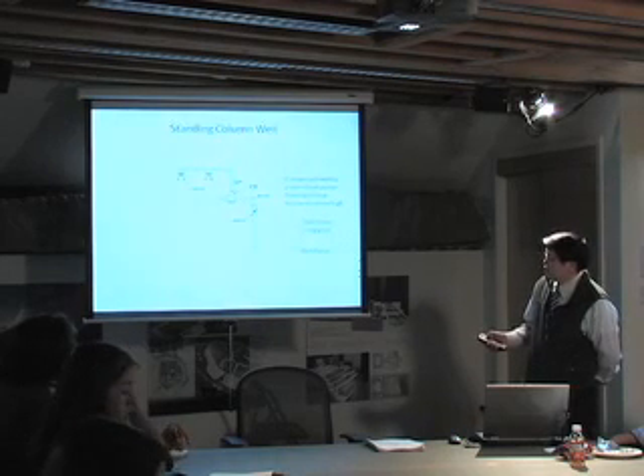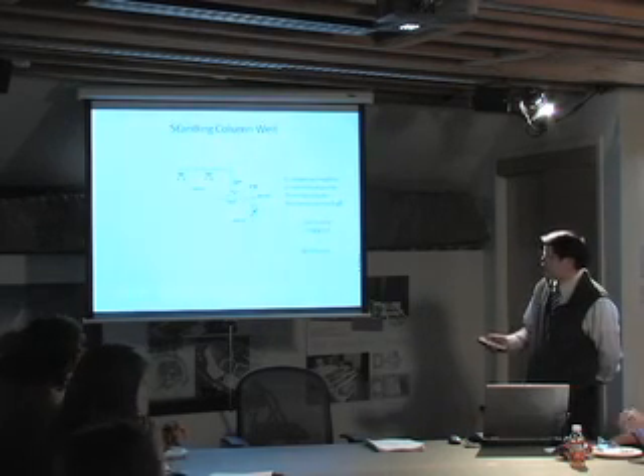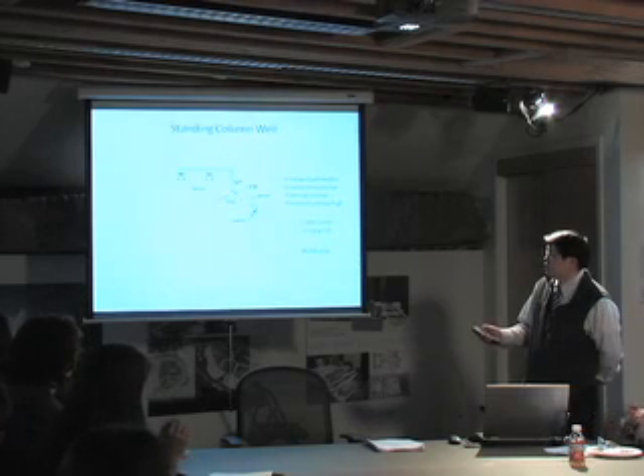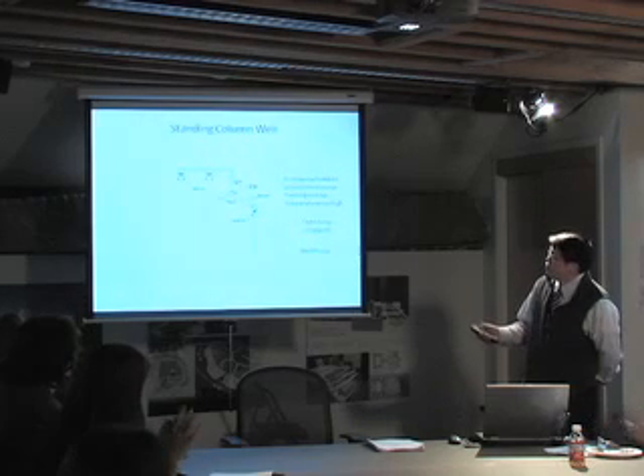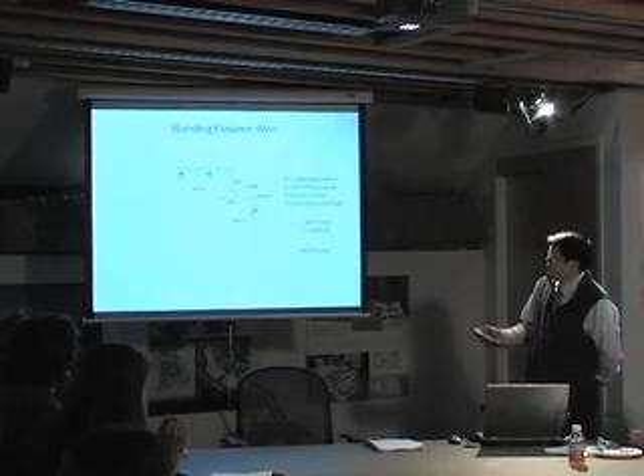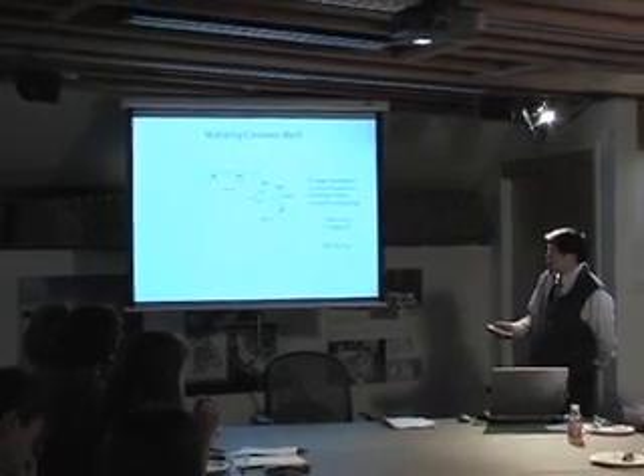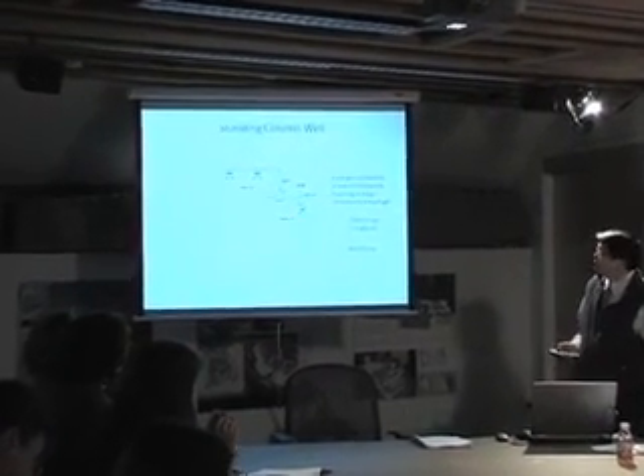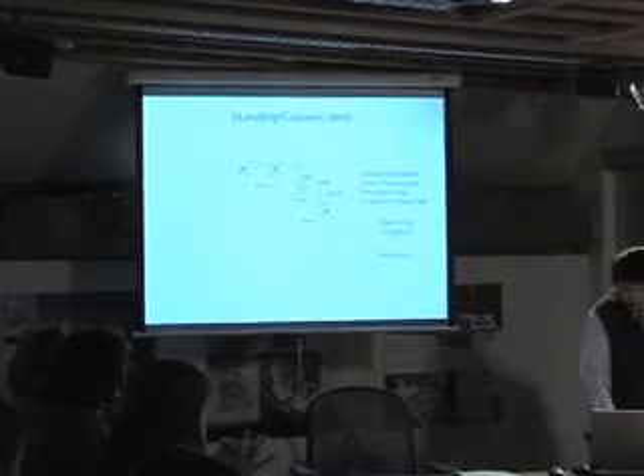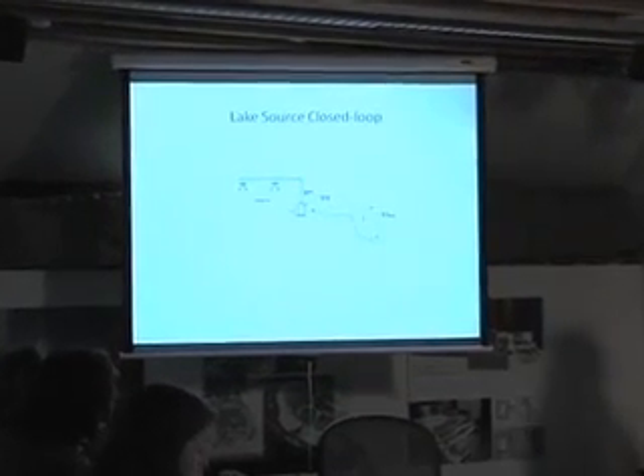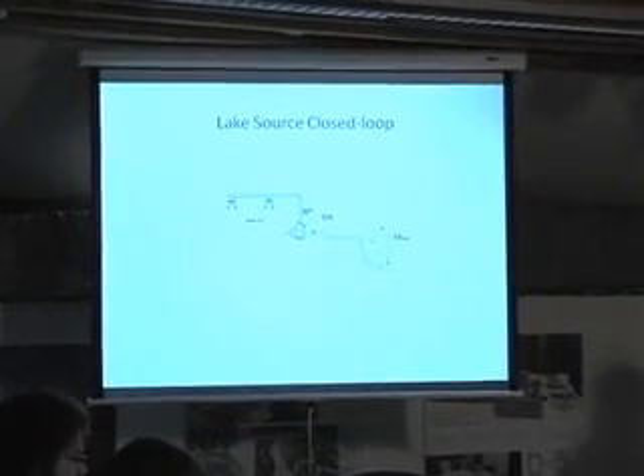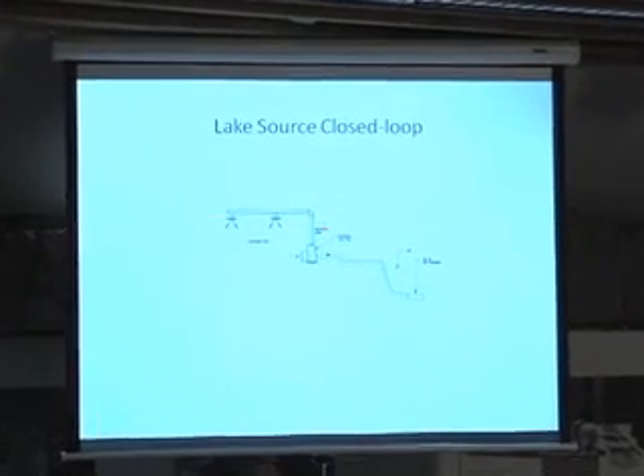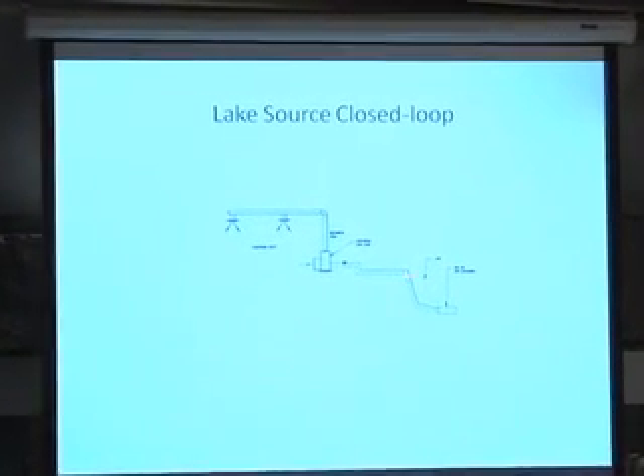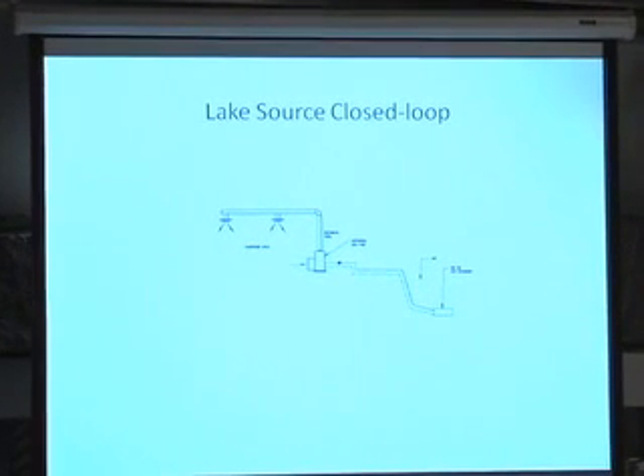And same deal for the cooling season. If the water gets too hot, as you are constantly rejecting heat into the well, you bleed some of the hot water here, and the surrounding cool water is going to make up to the well. Another configuration, if you have a large body of water near your building, like a lake or pond, it's very clear here. This is a pond here, a lake. Inside the building, mechanical room, you have a heat pump.